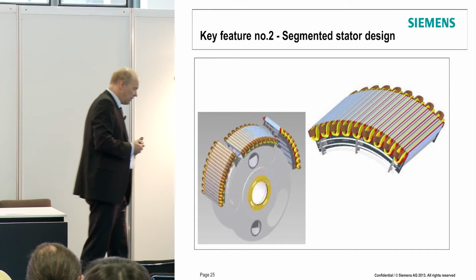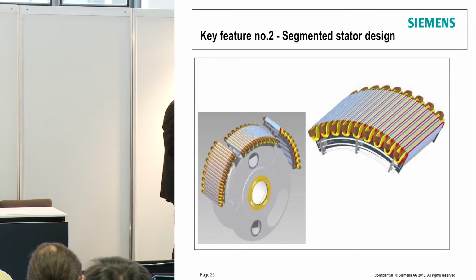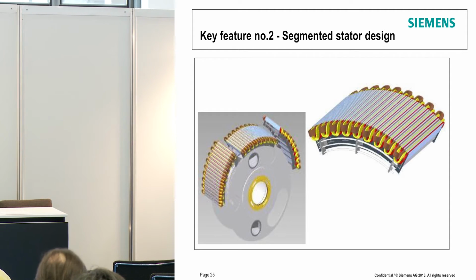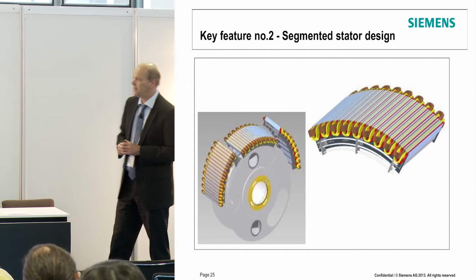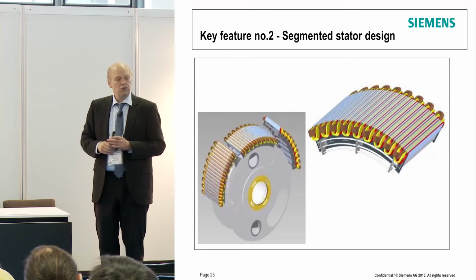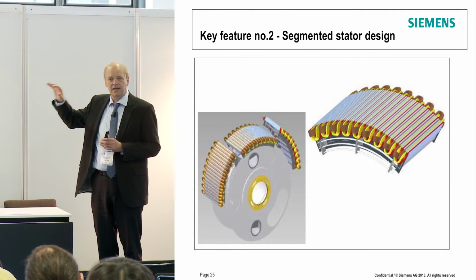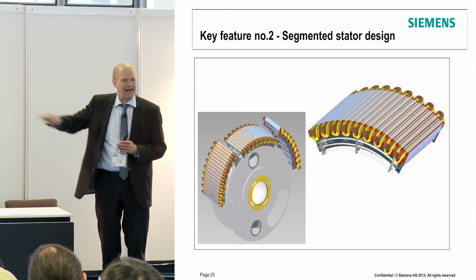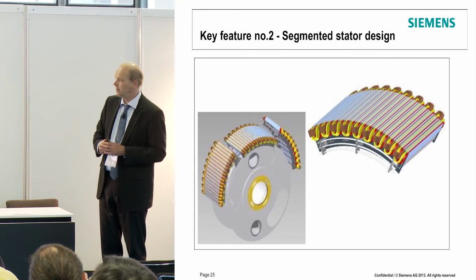But the difference is that they typically are done with completion of the winding after the stator has been installed. So you have open slots, and you install the last bit of the winding once the stator is installed. We needed a solution where the stator segments are truly independent and don't need any electrical wiring after they've been completed.